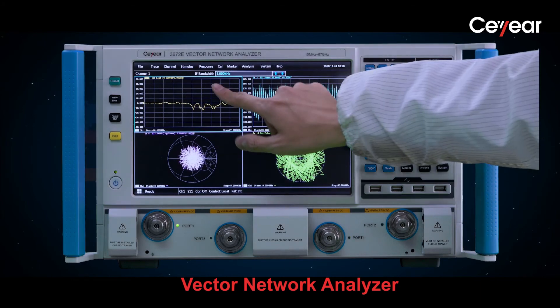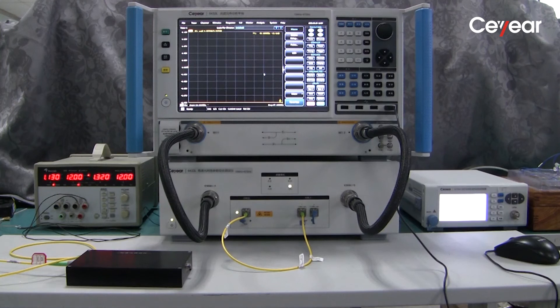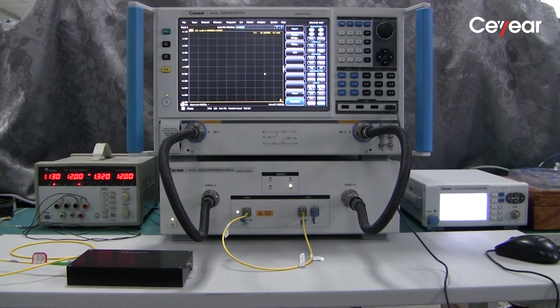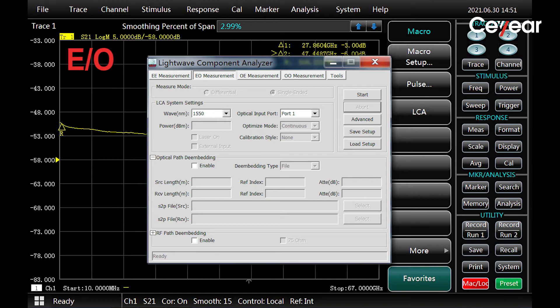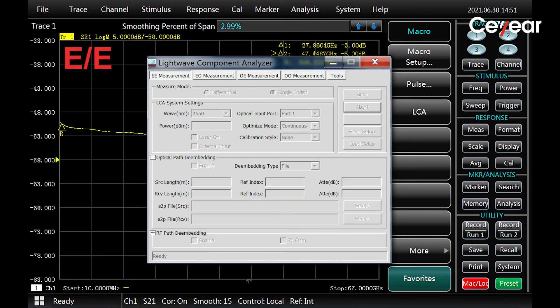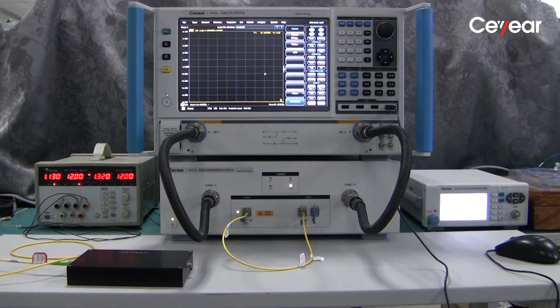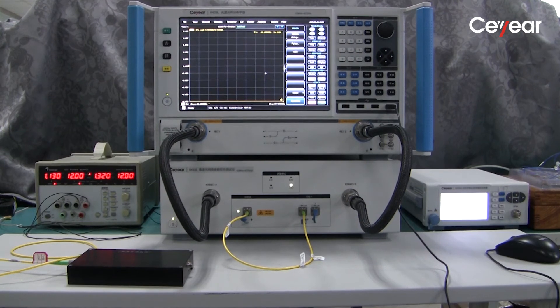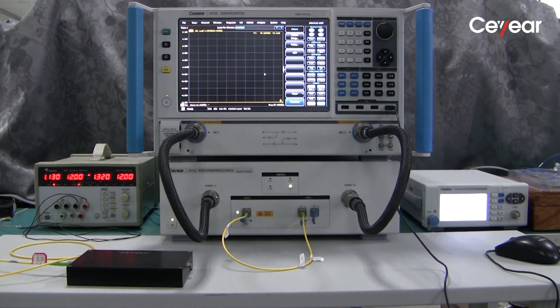Benefiting from the high-performance vector network analyzer, the light wave component analyzer, short for LCA, features EO, OE, OO, and EE working modes. It also has a built-in optical power meter. Today, I will show you how to test optical components.